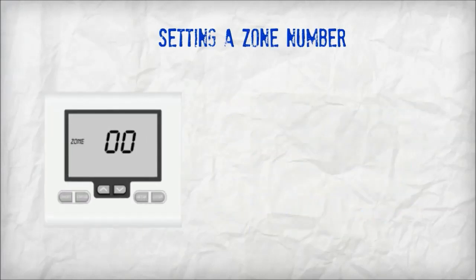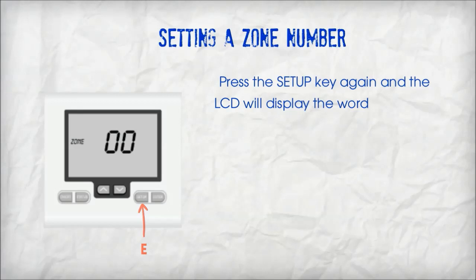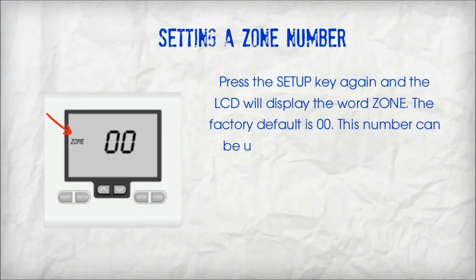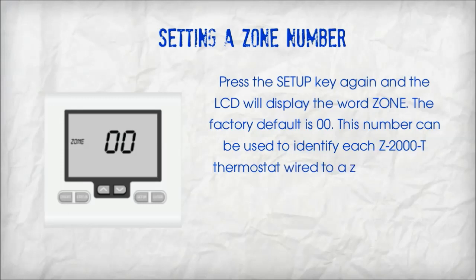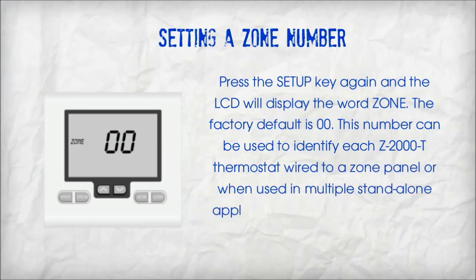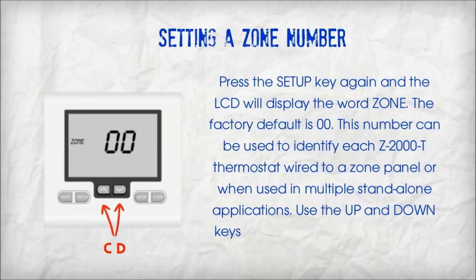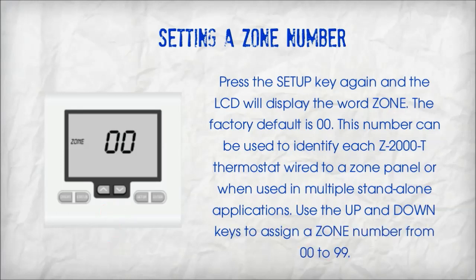Setting a zone number. Press the setup key again and the LCD will display the word 'zone'. The factory default is 00. This number can be used to identify each Z2000T thermostat wired to a zone panel or when used in multiple stand-alone applications. Use the up and down keys to assign a zone number from 00 to 99.